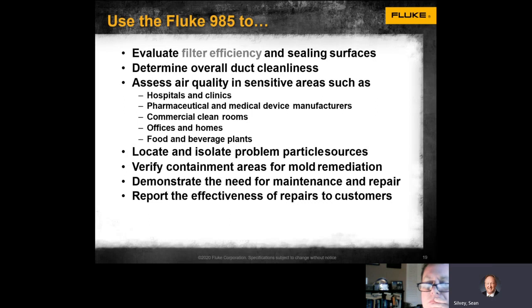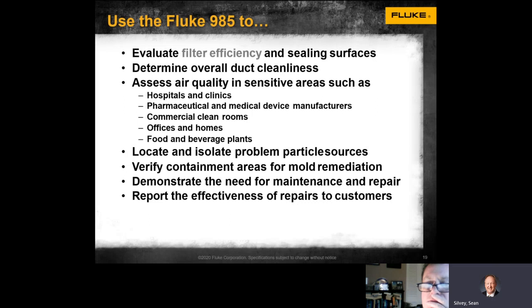The 985 is designed for larger particles. Note that smaller viruses are in the nanometer range, which this unit cannot detect. However, the 985 is crucial for identifying and locating larger problems like bacteria and mold. It helps evaluate filter efficiency, determine overall duct cleanliness, and assess air quality. Applications include hospitals, clinical facilities, pharmaceuticals, clean rooms, offices, homes, and food and beverage plants.